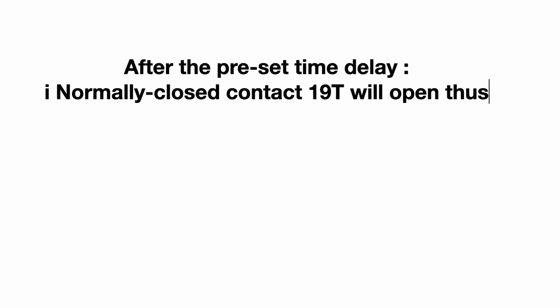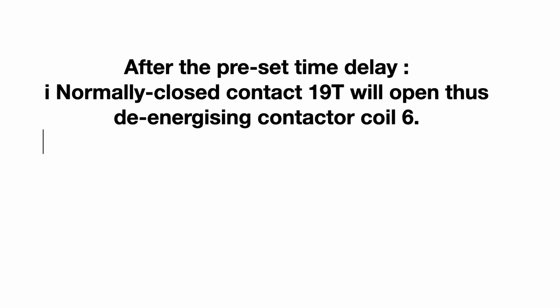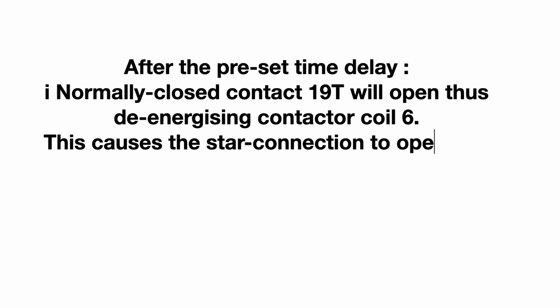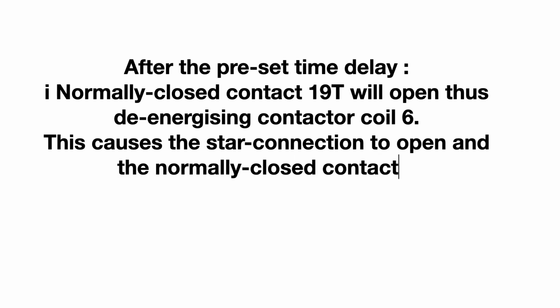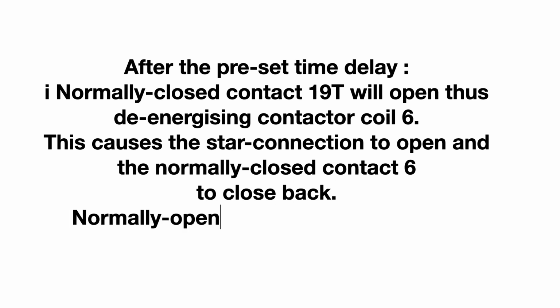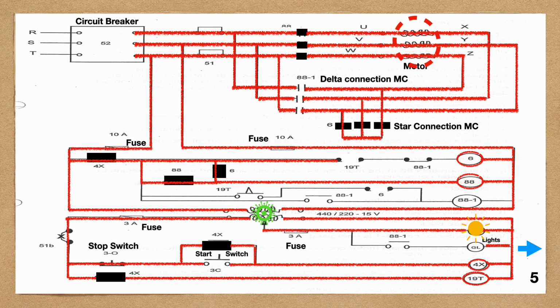After the preset time delay, normally closed contact 19T will open, thus de-energizing contactor coil 6. This causes the star connection to open and the normally closed contact 6 to close back. Normally open contact 19T will close.